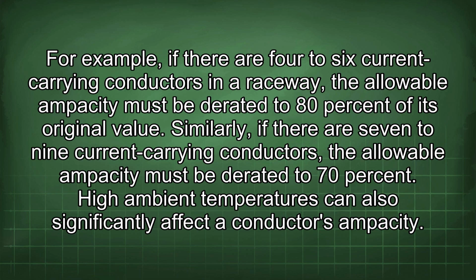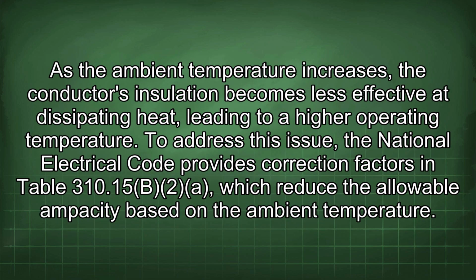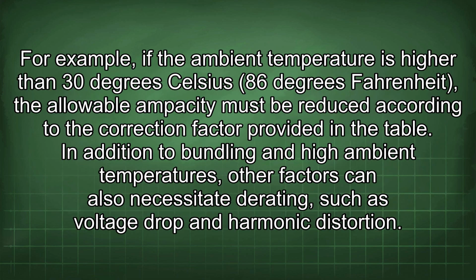High ambient temperatures can also significantly affect a conductor's ampacity. As the ambient temperature increases, the conductor's insulation becomes less effective at dissipating heat, leading to a higher operating temperature. To address this issue, the National Electrical Code provides correction factors in Table 310.15(B)(2), which reduce the allowable ampacity based on the ambient temperature. For example, if the ambient temperature is higher than 30 degrees Celsius (86 degrees Fahrenheit), the allowable ampacity must be reduced according to the correction factor provided in the table.